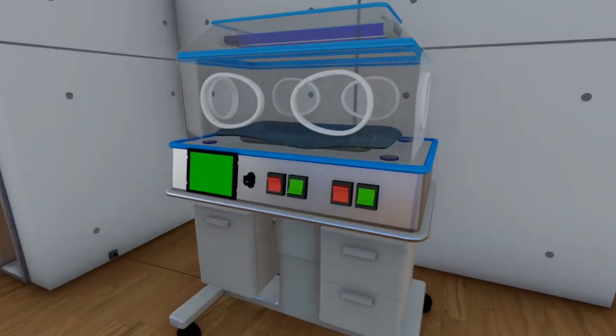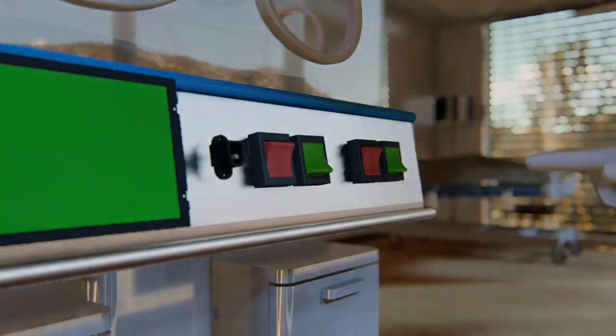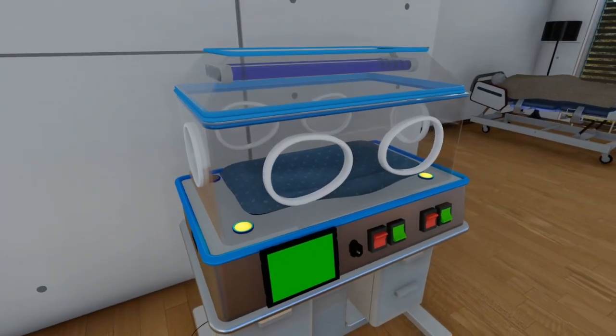When the system working on this multi-function incubator fails — for example, if only two bulbs are on — the buzzer will sound ten times and the LCD screen will show a system error with a ten-second countdown. After that, the system will shut down automatically.